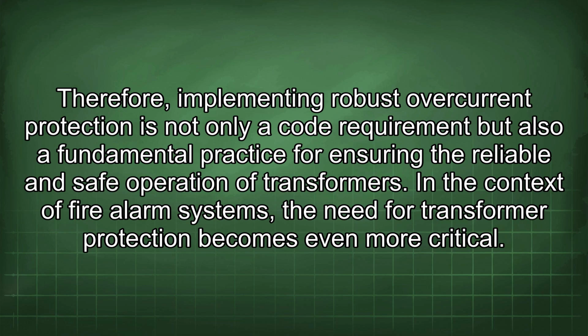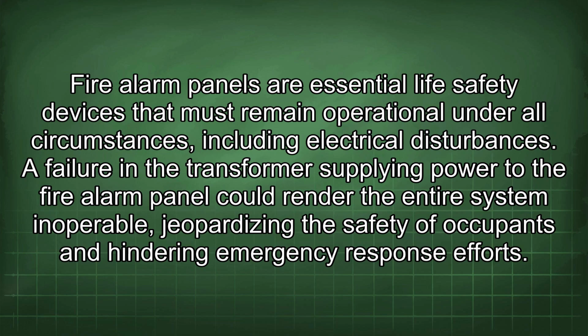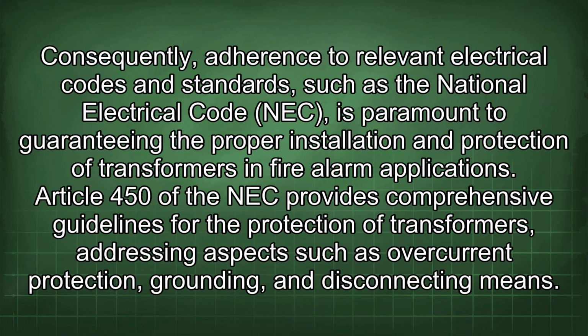In the context of fire alarm systems, the need for transformer protection becomes even more critical. Fire alarm panels are essential life safety devices that must remain operational under all circumstances, including electrical disturbances. A failure in the transformer supplying power to the fire alarm panel could render the entire system inoperable, jeopardizing the safety of occupants and hindering emergency response efforts. Consequently, adherence to relevant electrical codes and standards, such as the National Electrical Code (NEC), is paramount to guaranteeing the proper installation and protection of transformers in fire alarm applications.